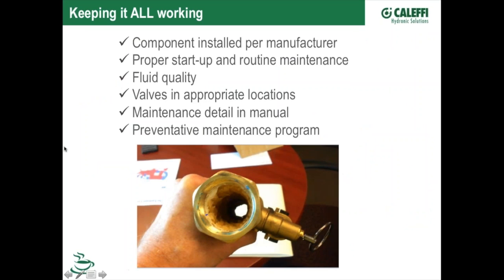All right, now we got to keep it all working. I showed you, again, a quick view of some of the products here. We'll get to some more next month. You got to be concerned about what you're putting in these valves. You know, we send the valves out with nice, clean, shiny brass inside of them. When we see a picture like that, we're concerned. What's going through that valve? That can cause problems in there with the flow regulation. Worst case scenario, we can actually close that opening right up and have a problem.